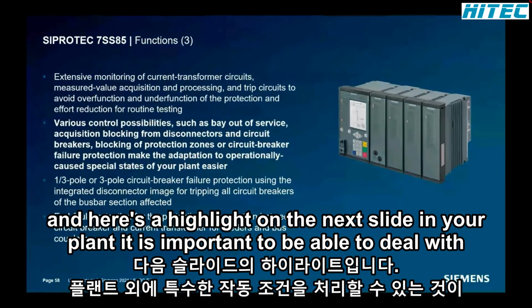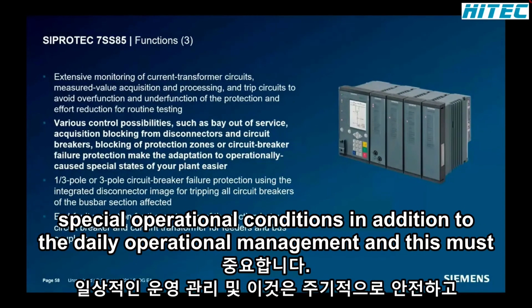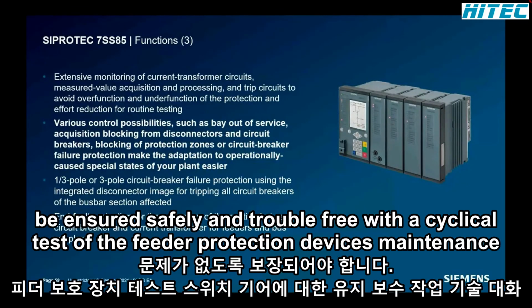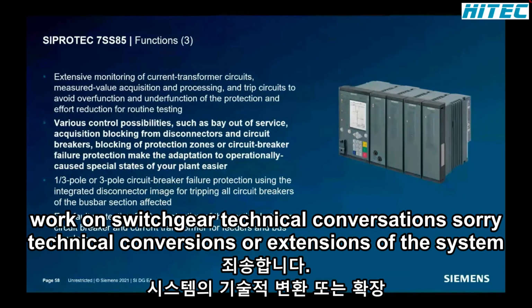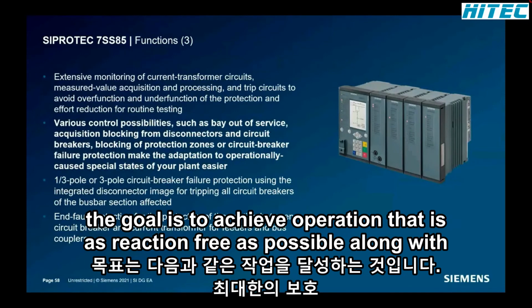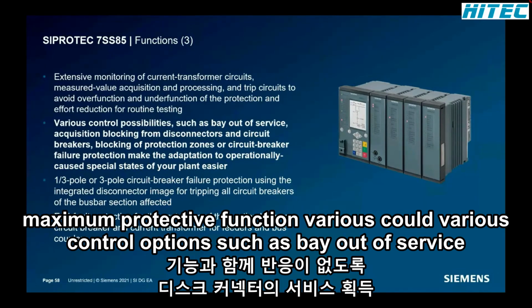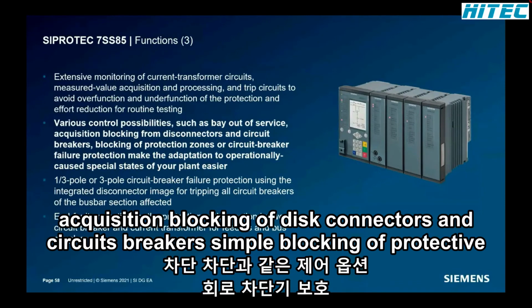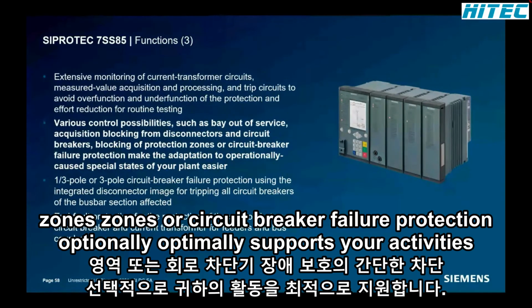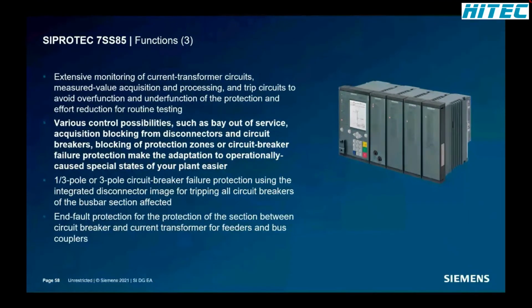And here's a highlight on the next slide. In your plant, it is important to be able to deal with special operational conditions in addition to the daily operational management. And this must be ensured safely and trouble-free. Whether cyclical tests of the feeder protection devices, maintenance work on switchgear, technical conversions or extensions of the system, the goal is to achieve operations that are as reaction-free as possible along with maximum protective function. Various control options such as bay out of service, acquisition blocking of disconnectors and circuit breakers, simple blocking of protective zones, or circuit breaker failure protection optimally supports your activities.